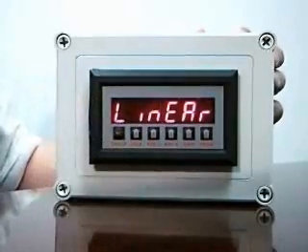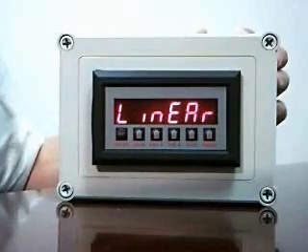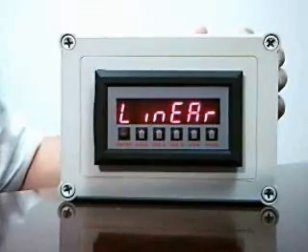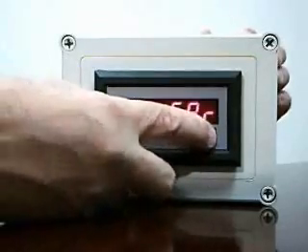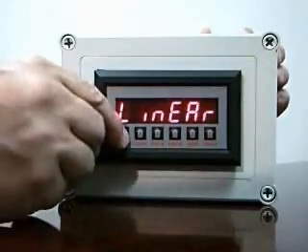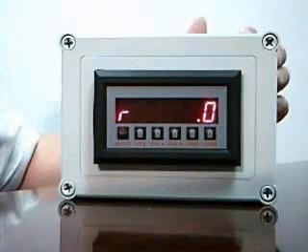At this point, it will ask me: is the input a linear signal, or is it one from an orifice plate or other square law device that needs to have a square root extraction done? You'll notice I can change to tell it that the signal is either a linear signal or a square root is required. After I've made my selection, it returns to the run mode, as indicated by the R in the far left.